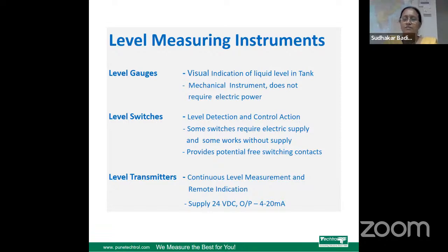The next is level transmitters, and these level transmitters are used for continuous level measurement and remote indication. It provides 4 to 20 milliampere output, and this 4 to 20 milliampere output can be transmitted over a long distance. And you can connect these 4 to 20 milliampere to various indicators or PLC or SCADA, and you can see the liquid level on it.